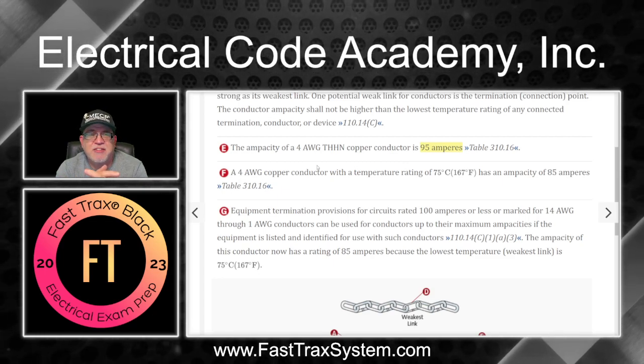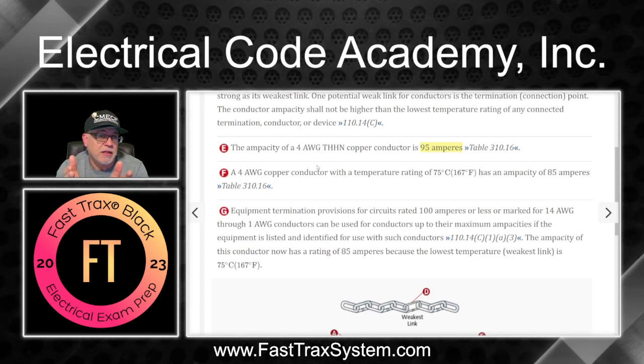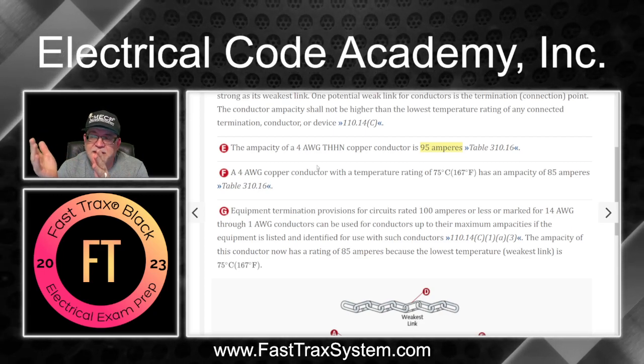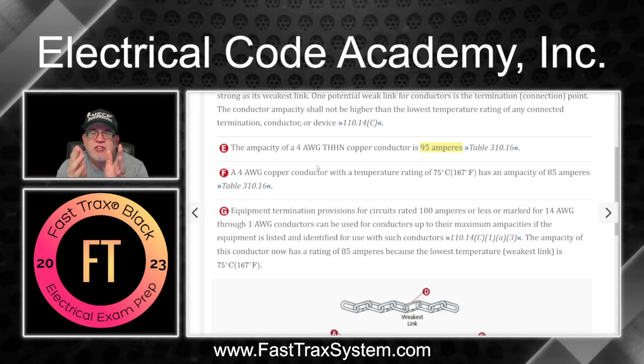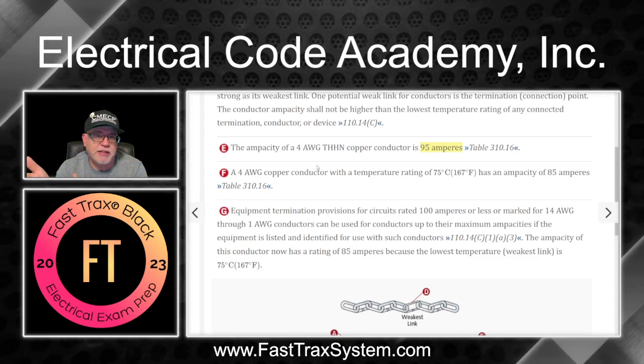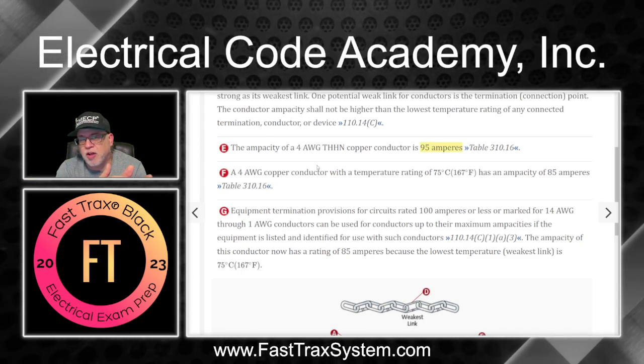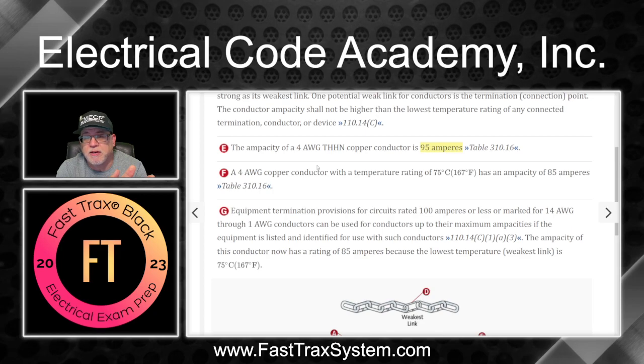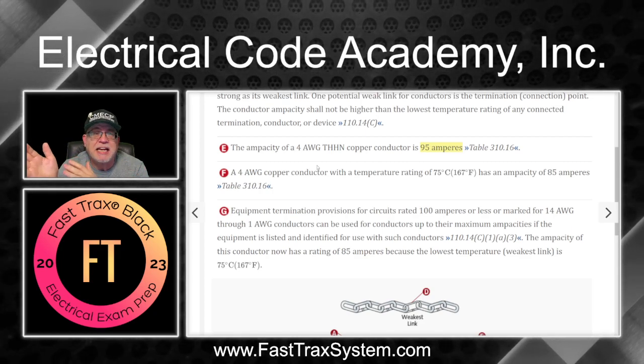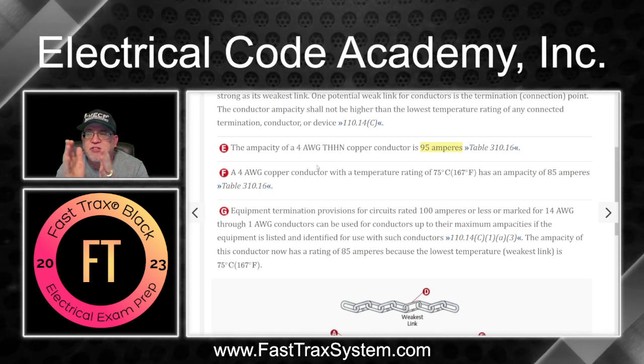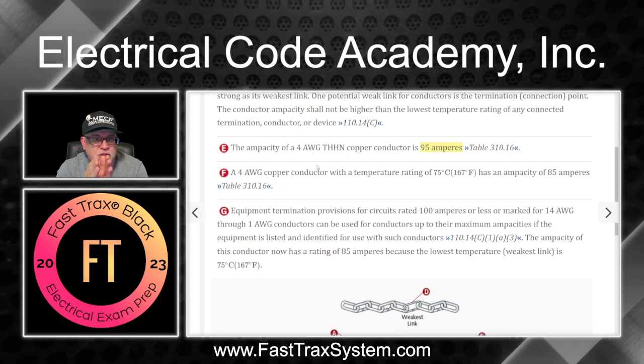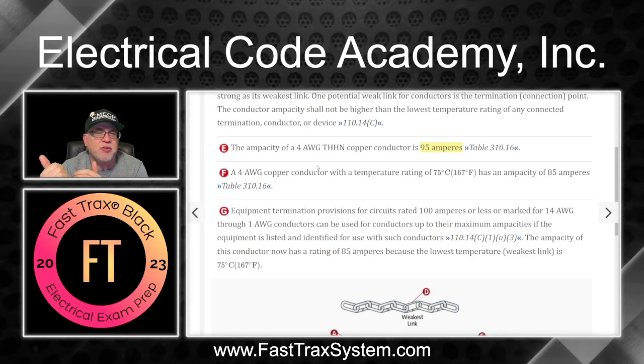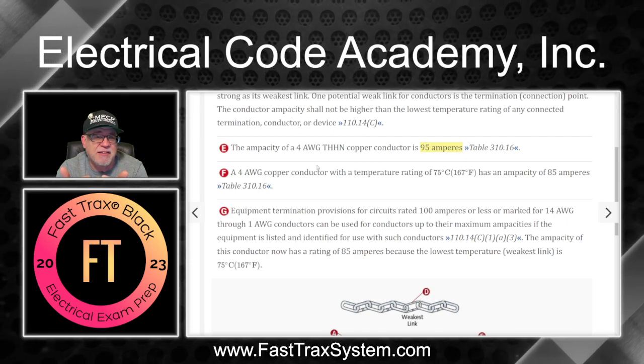The conductor has an insulation rating of 90. I can use that 95 amps to adjust and correct for a number of current carrying conductors or ambient temperature that's other than 30 degrees Celsius, 86 degrees Fahrenheit. But I still have my limitations per the terminals, which is 75. So I still can't exceed the 75.